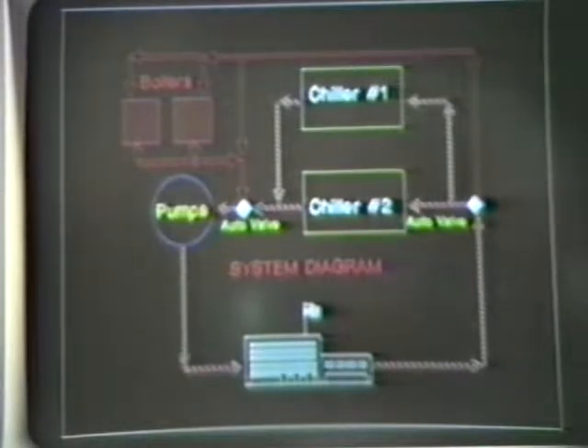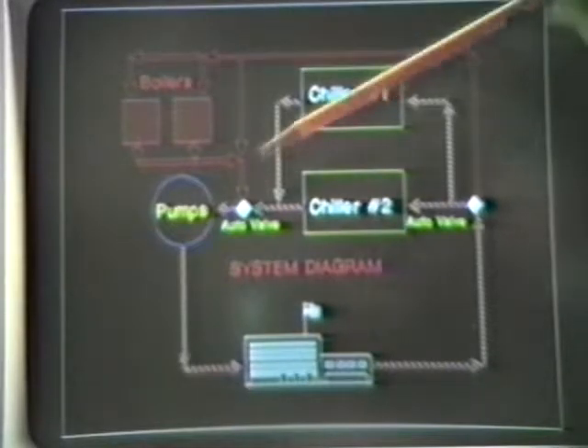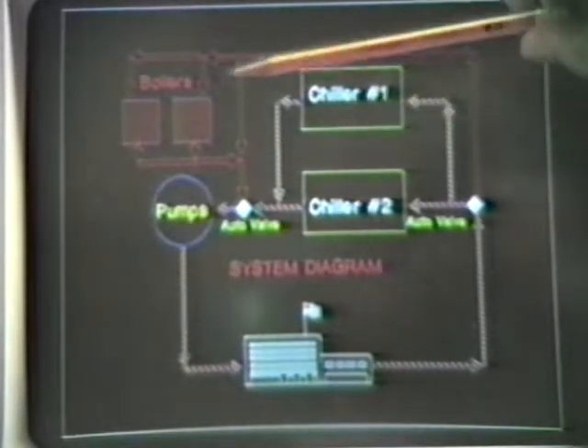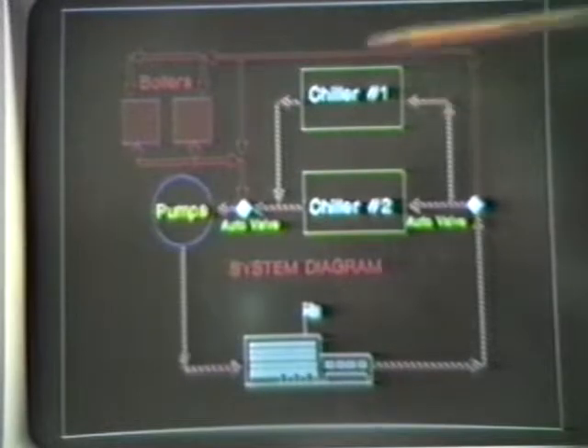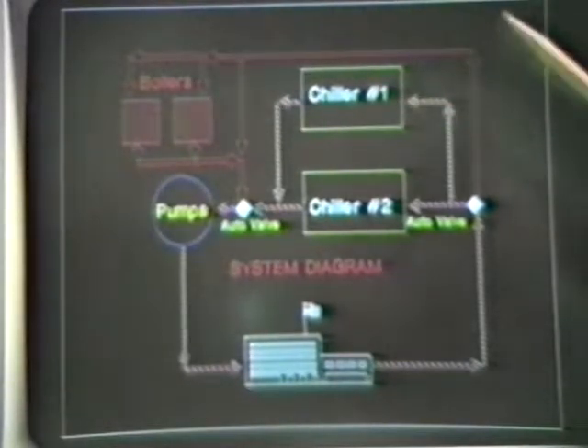Let's discuss our changeover procedure from chill water to hot water in the central plant. Here we see our system in the chill water mode going through the chillers, pumps into the buildings. From our main control panel in the equipment room, the systems can be changed from air conditioning or chill water to hot water. When we do this, valves will open either to the boilers, closing it from the chillers, or vice versa.